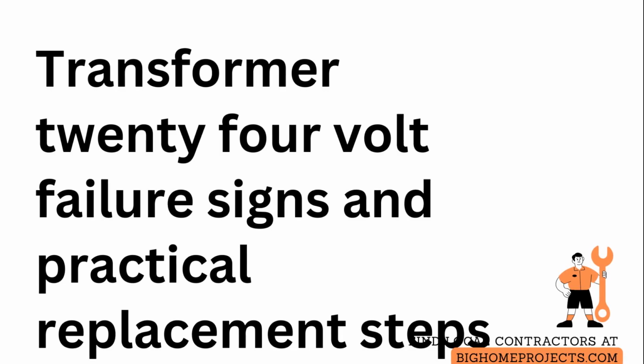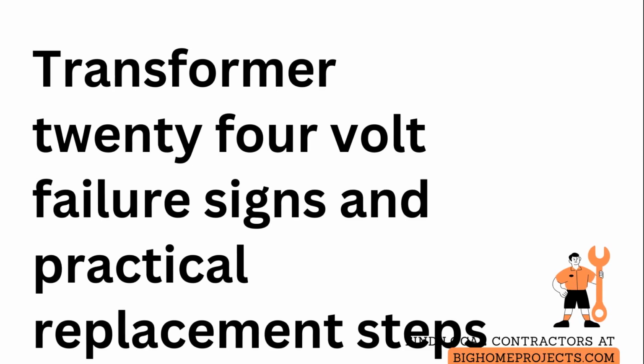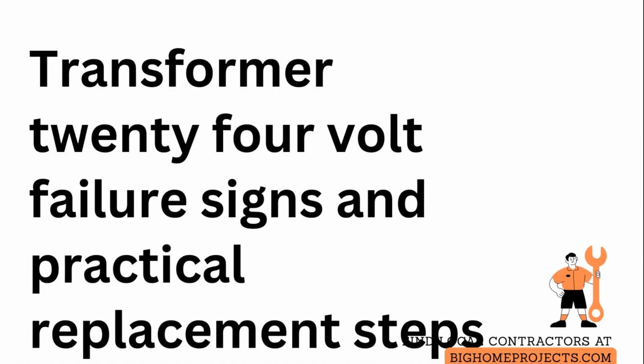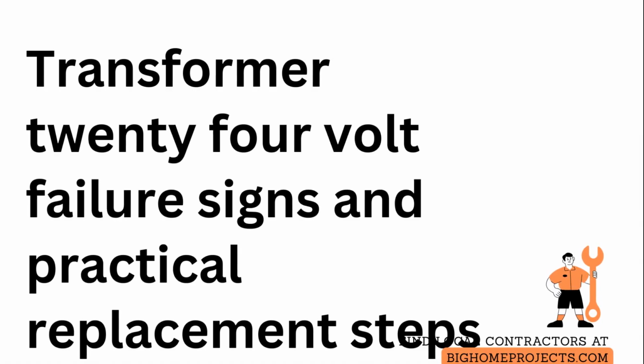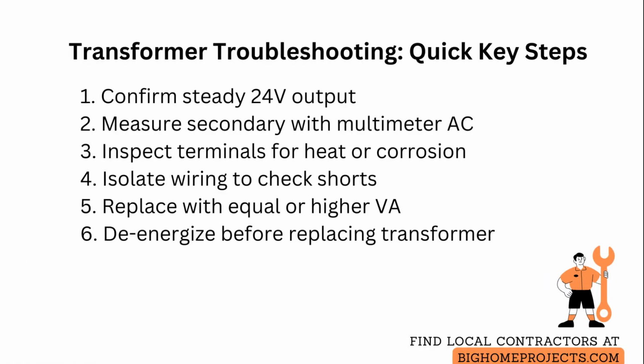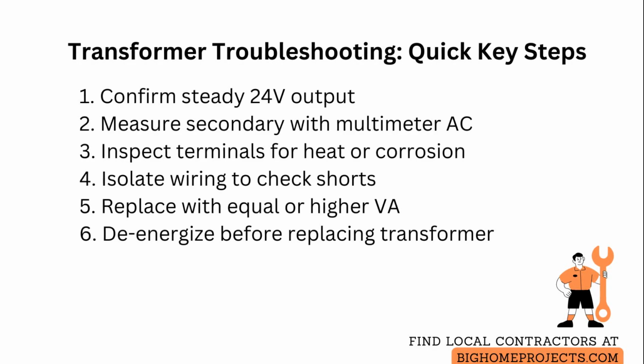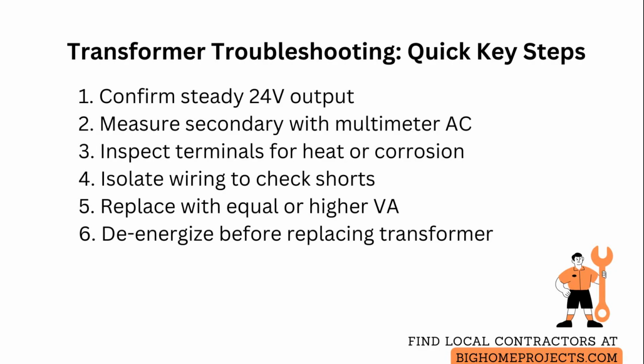The transformer provides the low voltage reference that allows the blower motor control and the thermostat to communicate and operate properly. The transformer converts the high voltage incoming power to 24-volt alternating current that feeds the entire control circuit, including the thermostat, relays, control board, and safety devices.